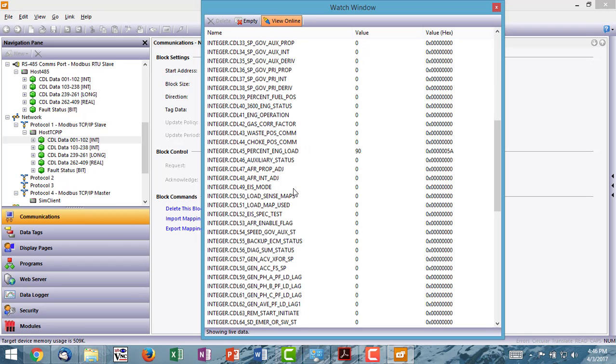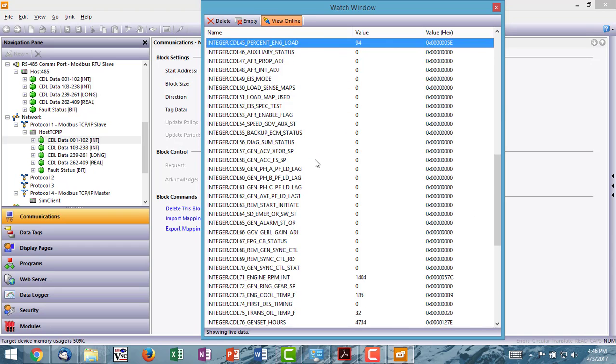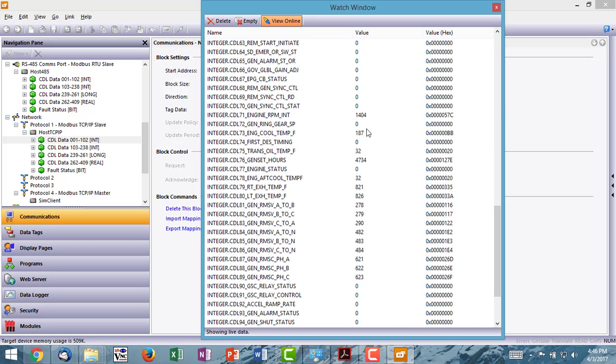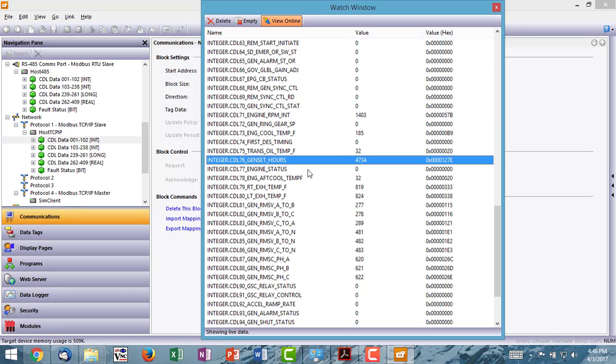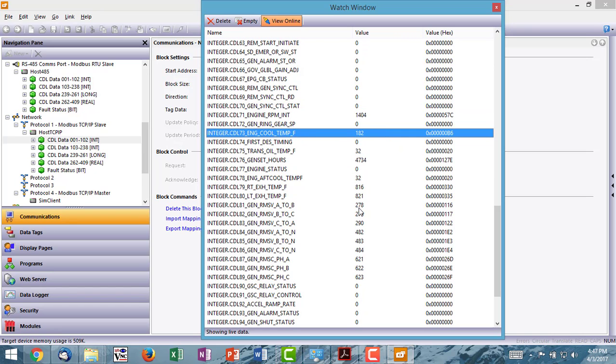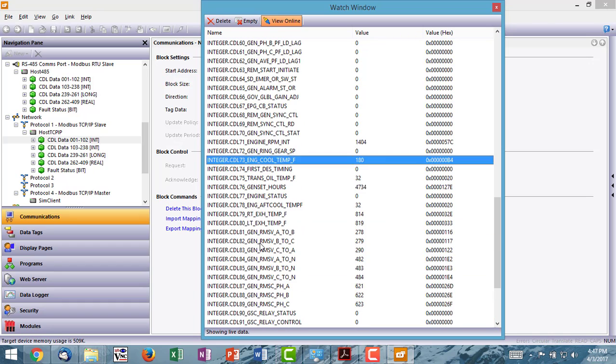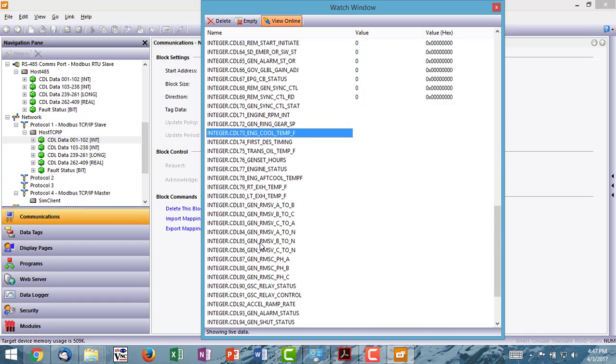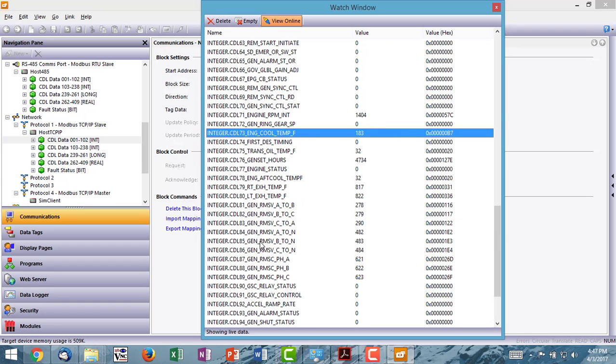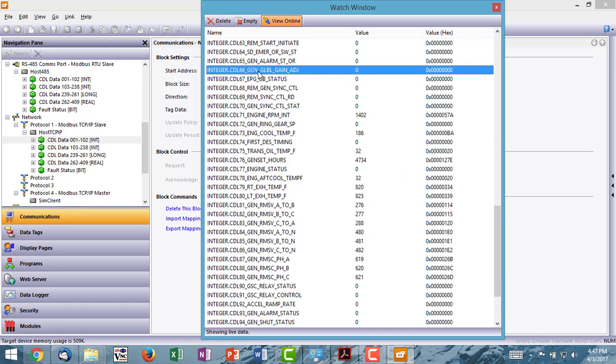And you'll see that there are an awful lot of zeros here. You can see one engine load is changing there. And we've got engine RPM, genset hours, and coolant temp. So a couple of things to note. You're not going to see data for every one of these values. The values that you will see data on are whatever is available on your engine. So if you see a zero here, chances are that value is not available on your engine or on your genset.